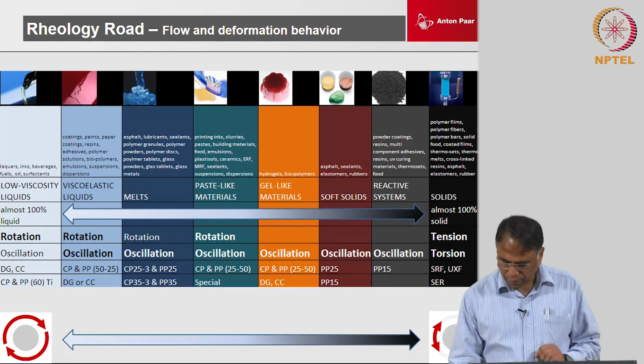Maybe for viscoelastic liquid measurements you may require a 50 mm geometry, but for viscoelastic solids you will require a 25 mm geometry. And further down, if you go to very strong solids like thermosets, where you are doing curing experiments, then generally we use PP parallel plate geometries like 12 mm, 8 mm. They become smaller in size because the interaction measured over these small surface areas is sufficient to characterize the sample and get the required information.